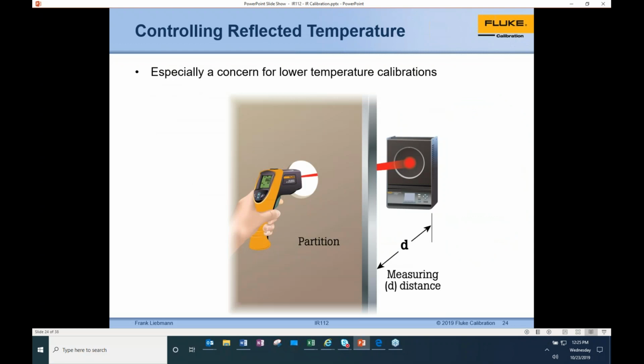In this example, I'm showing you the use of a partition. Here you can see we go back to that measuring distance, measuring height, and we get our reading. The partitions can be used more so at lower temperatures, to test if the testing you're doing at lower temperatures is being impacted by emitted energy you're not seeing. You can build a really simple partition out of cardboard or something and take your measurement using a partition versus not using it. You may find it not necessary, but if you do see a difference in your reading, there's a good chance there's some radiated energy beyond the target impacting your readings that you're not aware of. So it's kind of a test it, see if you get a difference situation. What the partition is doing is allowing basically noise or scatter - it's limiting how much the optics can be impacted by that coming back in, by limiting the field of view up close.